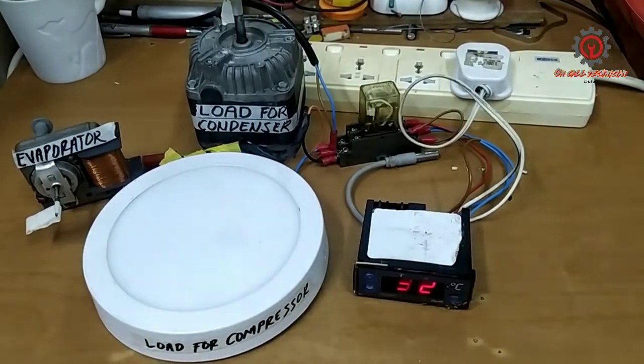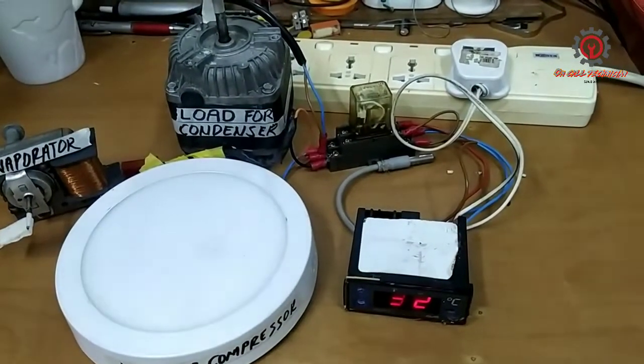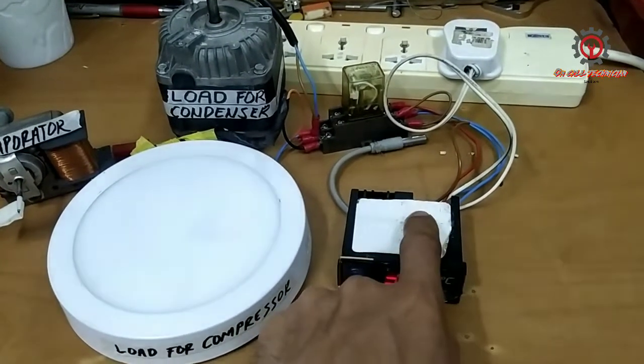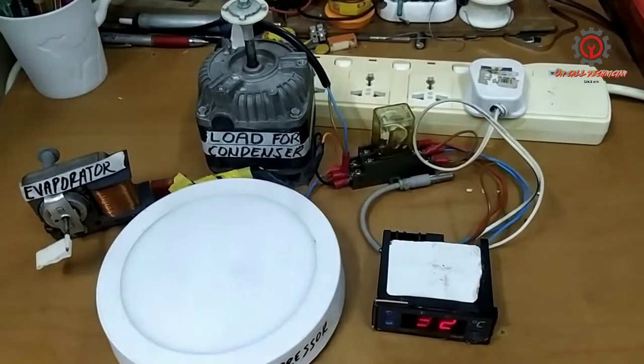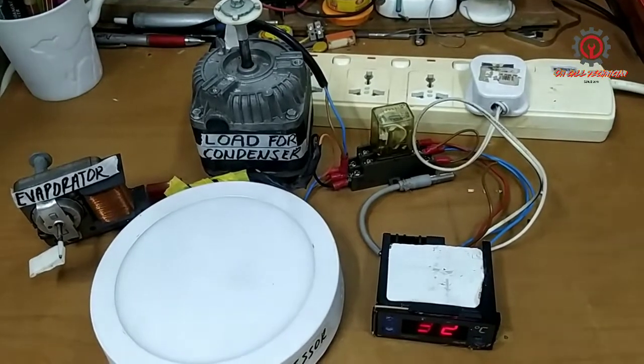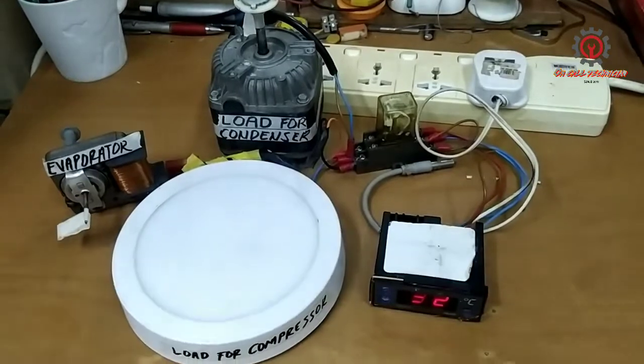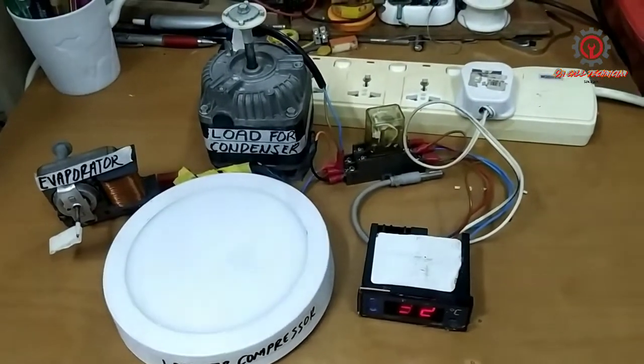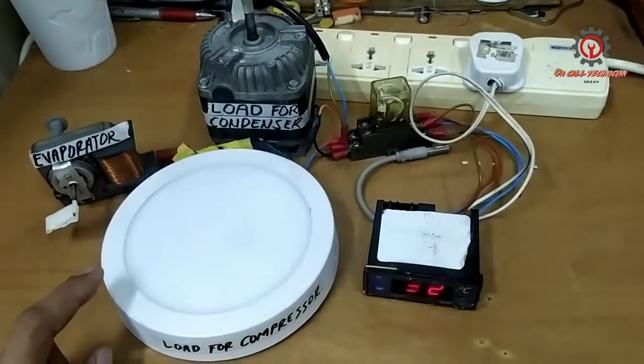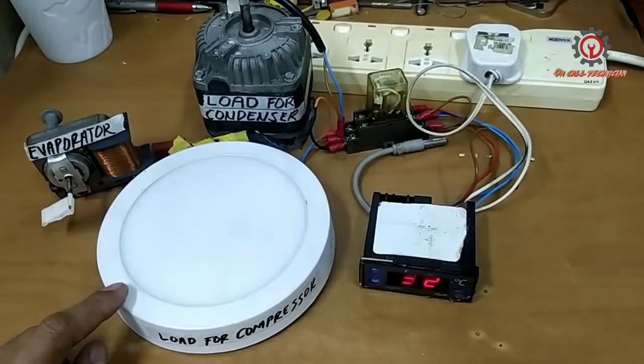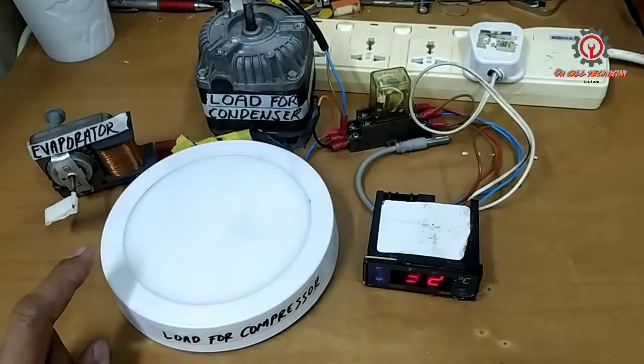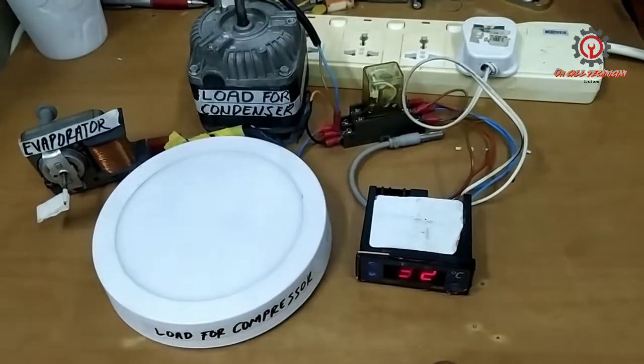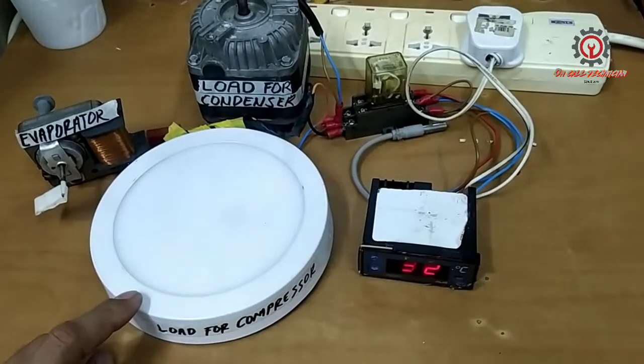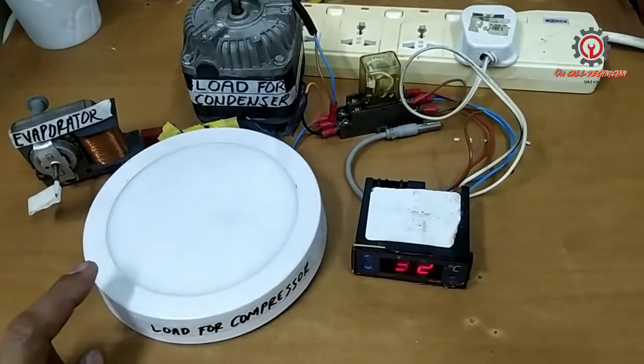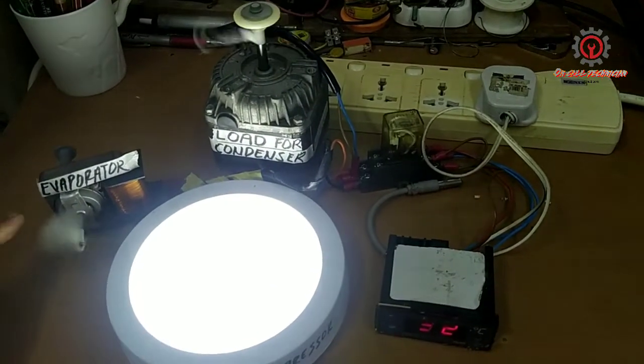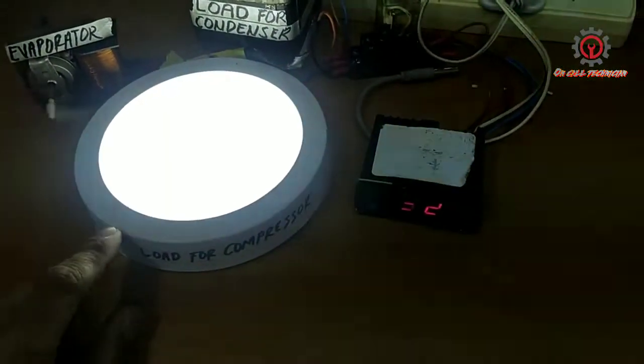The reason we installed 2 dual pole, dual throw relays is so that the relay here will not overload, because it's only rated 8 ampere, just in case your compressor is 1.5 HP or 2 HP. It already meets the 8 ampere during startup, because startup of the compressor is almost double the ampere of the compressor. And there, guys, evaporator on, condenser on, and the load for the compressor is on also.